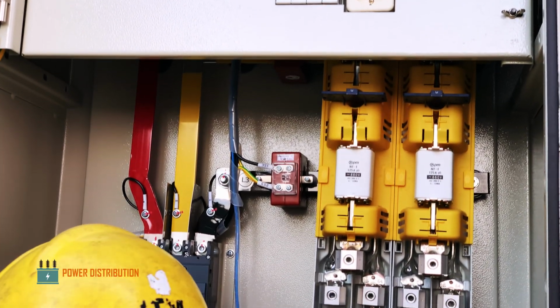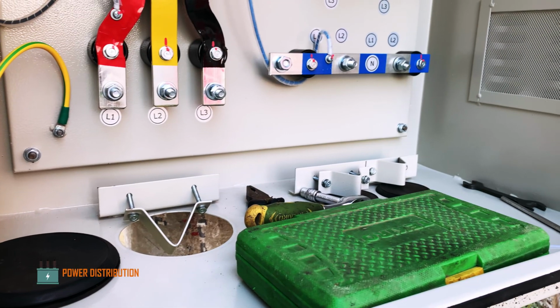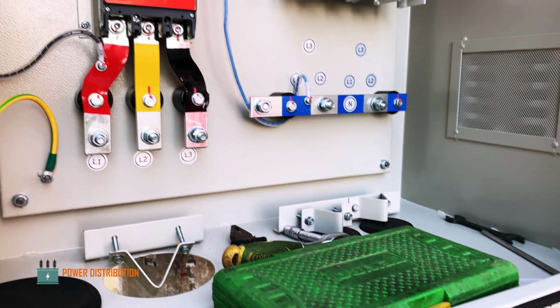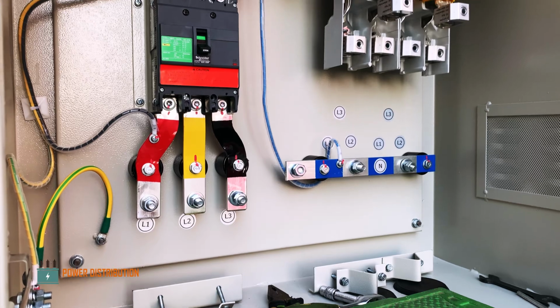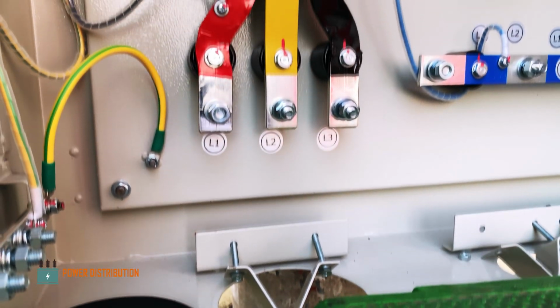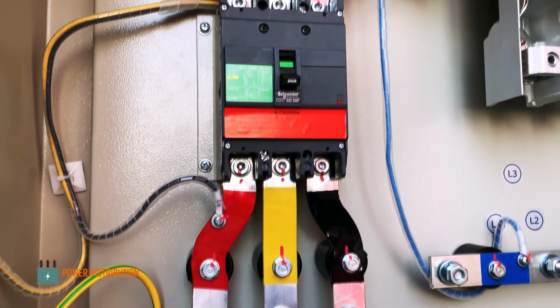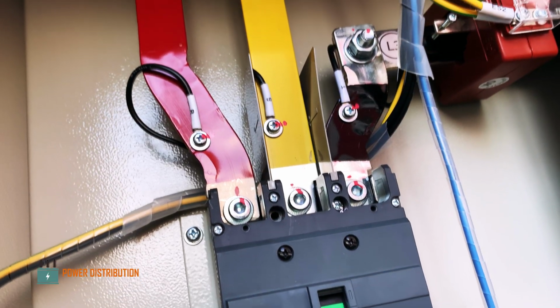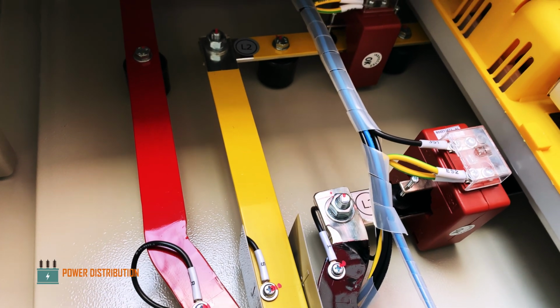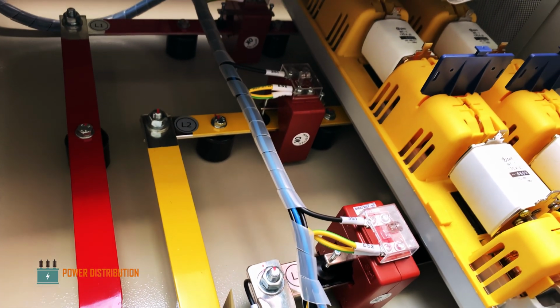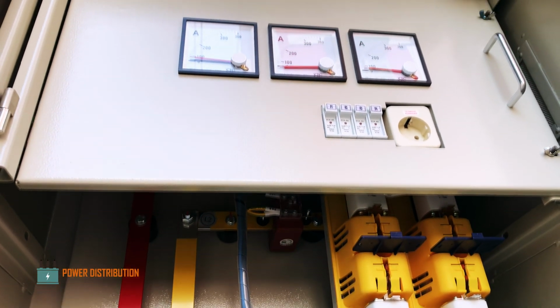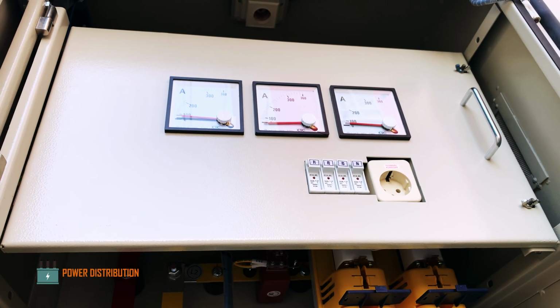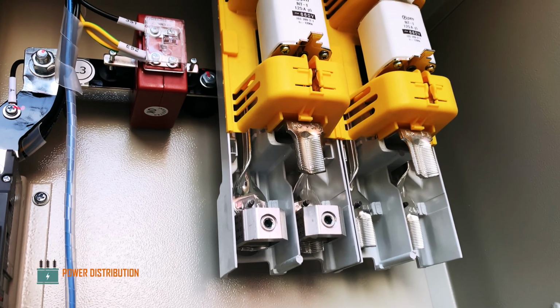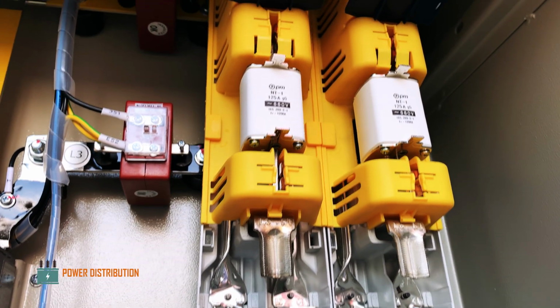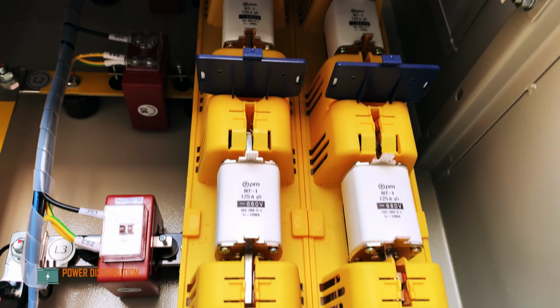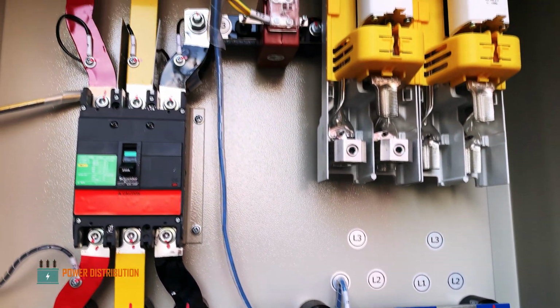Let's take a look what inside this LVMDP box. First, we have these two gigantic hole for the entry and exit for distribution cables, and then we have this non-fuse breaker or the breaker of this distribution box. There are three independent current transformer for each phases, measuring the current and displaying on the ampere meter on the top. Then we have this NT or NH fuse for each buses. Last but not least, the neutral bus.